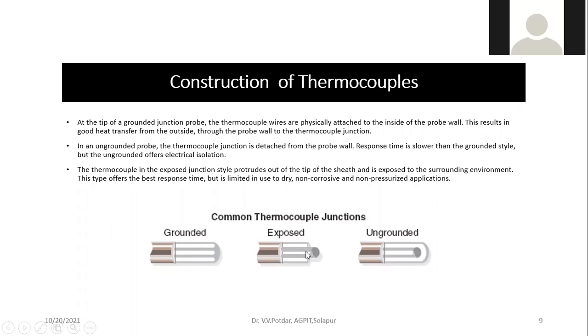Right? So I have got the casing limited to this, and the junction is protruding outside the casing. So that is the exposed type of thermocouple junction. Quickly we'll see. At the tip of the grounded junction probe, thermocouple wires are physically attached to the inside of the probe wall. This results in good heat transfer from the outside through the probe wall to the thermocouple junction. Okay, so it provides me better output voltage because it is giving me better temperature gradient.